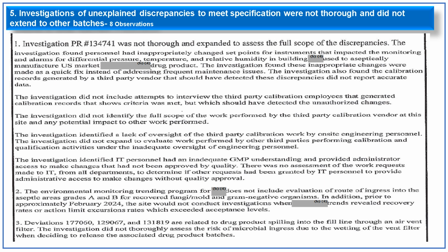any other potential impact. The investigation identified a lack of oversight of the third-party calibration work by on-site engineering personnel, and it did not expand to evaluate work performed by other third parties performing calibration and qualification activities. This investigation also identified that IT personnel had an inadequate GMP understanding and provided administrator access to persons who had not been approved by quality. There was no assessment of the work requests made to IT from all departments to determine if these requests had been granted by IT personnel to provide administrative access.